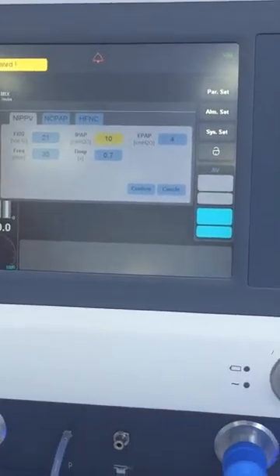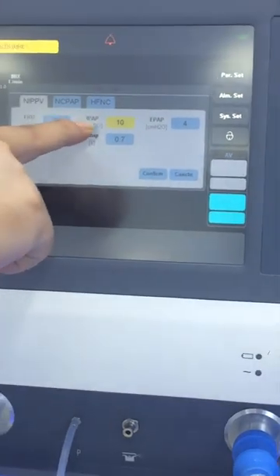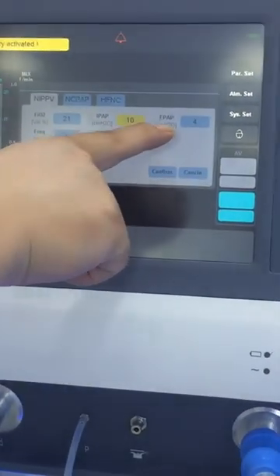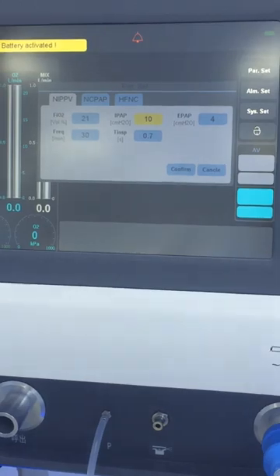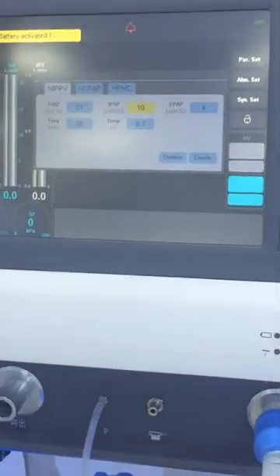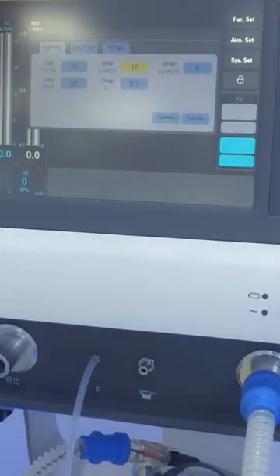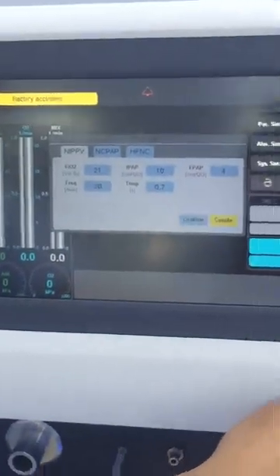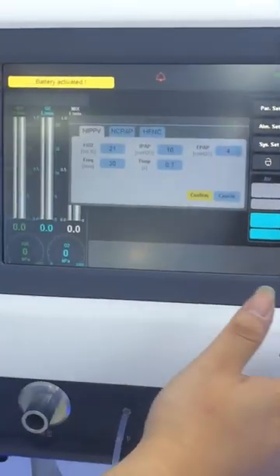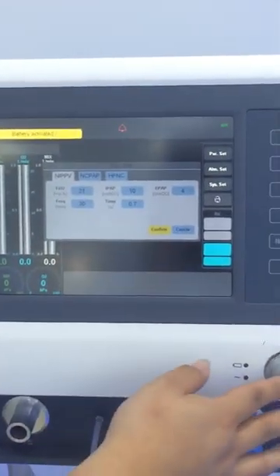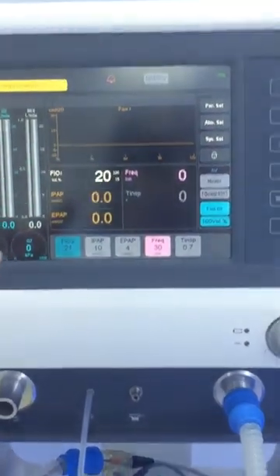Under the NIPPV, as we mentioned, it's the BiPAP function. So of course we can adjust both the IPAP and the EPAP. The IPAP means the inspiration pressure, and the EPAP means the expiration pressure. So BiPAP means that we can separately adjust the inspiration pressure and the expiration pressure. That's why we call it BiPAP. After all the parameters have been set, we move to confirm and press the button, or we can also press on the screen. So this will be the main interface.